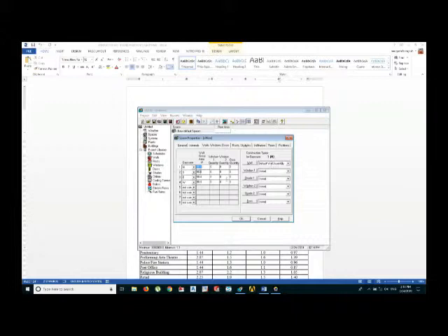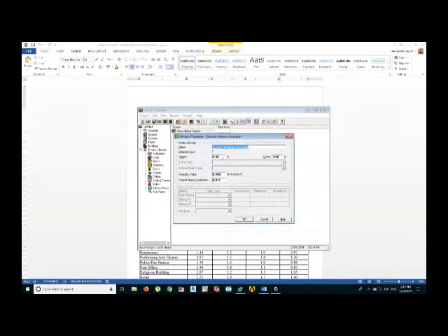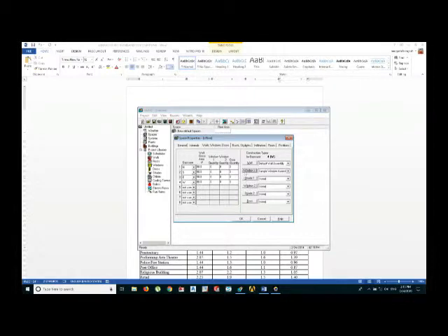This is the wall 1 wall assembly. For wall 2, use the same. For wall 3, for wall 4, these all are the same walls. If you have walls that are different, one is a different material, the second one is a different material, you can define these materials here in wall assembly. Second one is the window assembly. You can define the window assembly, its height, width, and the outer glazing, like it may be a gray tint, bronze tint, clear. My one is clear, so I will select 1 by 8, and size is 5 by 4. Just press OK. This is the window assembly.